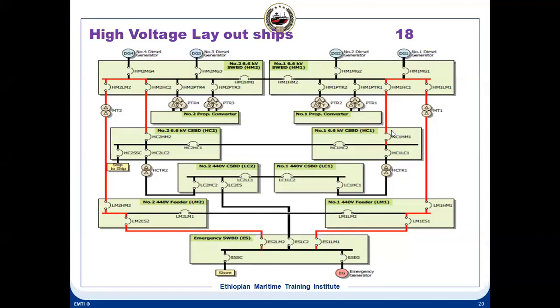Okay. You know how the layout is like this, just to have a concept of the layout. As I told you, these are the tie breakers to isolate the switchboard. You need to isolate this one. You can even isolate only this one, that is good enough. But for safety, normally you can isolate this also. This can be done locally, and you can also trip these breakers remotely to isolate the switchboard. Isolation is needed only when you want to isolate the switchboard for maintenance purposes or something. If you want to totally isolate it, you can open the tie breaker and then isolate this switchboard.